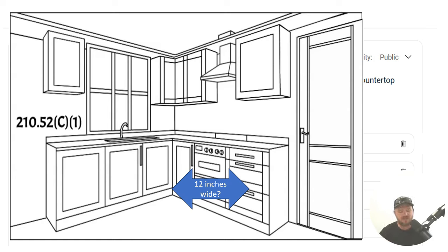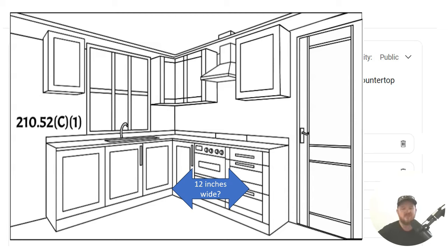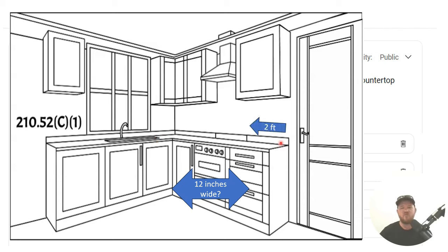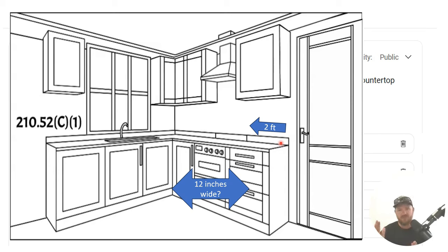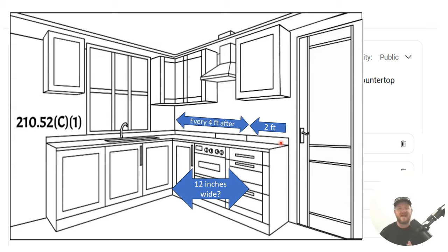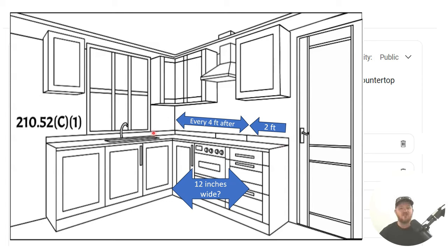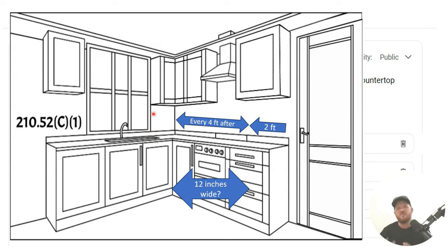It says receptacle outlets must be installed so that no point along the wall line is greater than 24 inches. Let's see what it's saying. You can pick either side of this countertop, starting with the sink here or over here to the right. And we're going to start with our first two foot measurement. So from the edge over two feet, we have to have our first receptacle within that first two feet. Then we're allowed to go up to four feet after that, just so that no point measured anywhere is going to be greater than two feet if you measure it. Then we need to wrap around this corner and we also need to finish within two foot of this sink right here in this specific scenario. And what the purpose of this is, is so you can plug in an appliance with a two foot cord and you should be able to plug it in basically anywhere that you set it down.